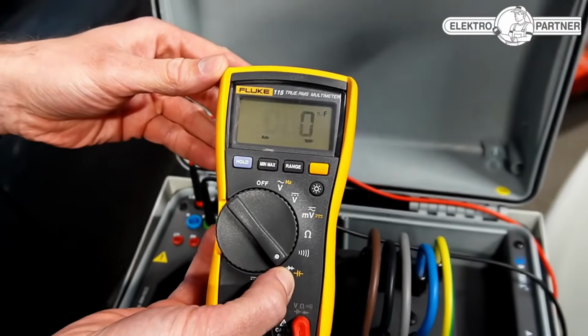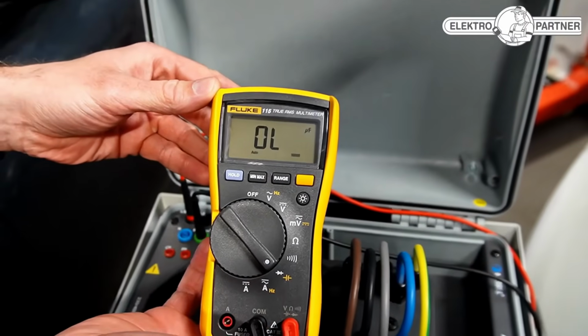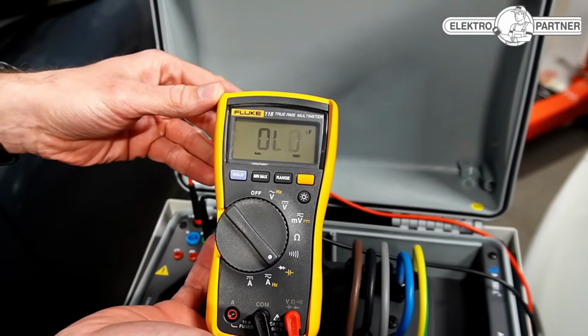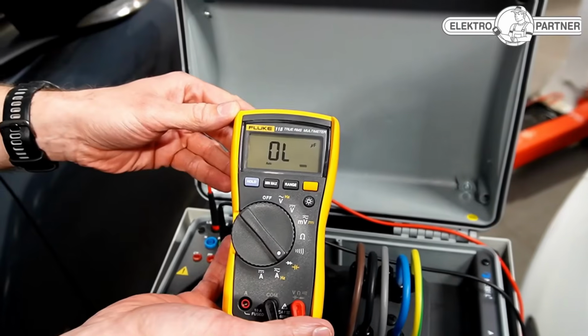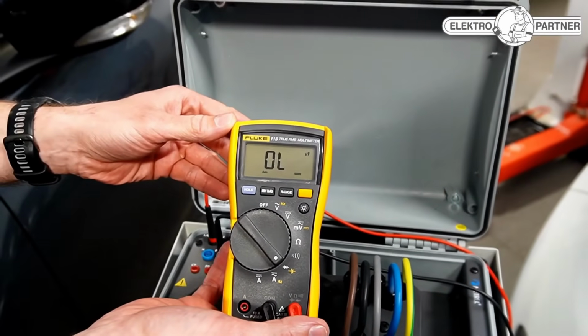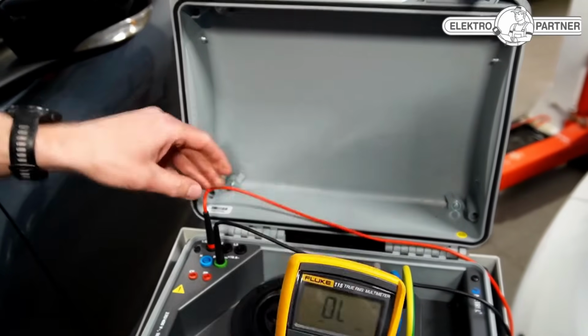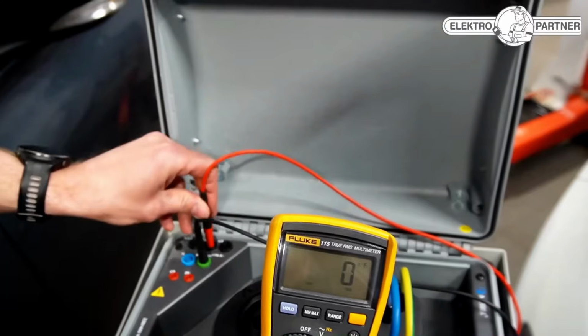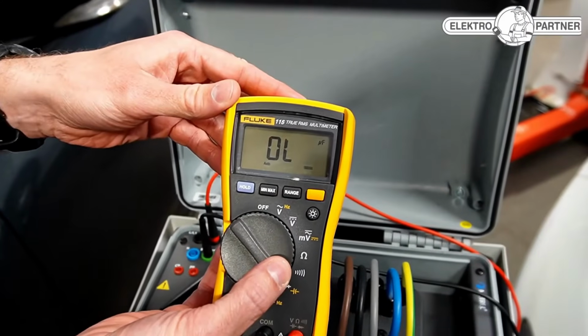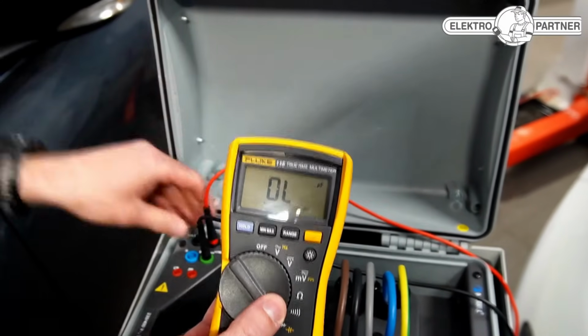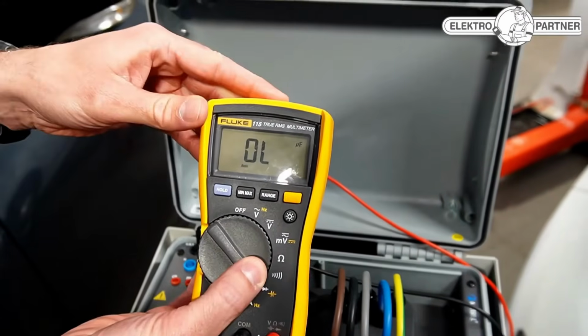Looking at the measurement, it's fluctuating between no connection, OL, and 0. So at first glance, it's not the 115 microfarads prescribed. We can try moving it to phase 2 - let's see if it does the same. It does. We'll move to phase 3 to check, and it does the same again.